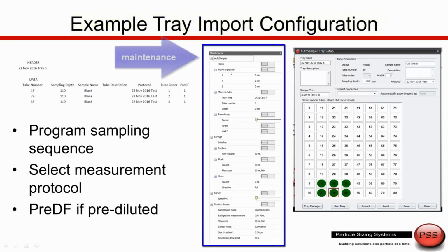The other screen you see in the middle here is just a maintenance screen where we can make sure that things are operating properly, move the tube, move the syringe, make sure that we've initiated everything and aligned the auto sampler. So this is just some screens showing how we set up the system prior to the measurement.